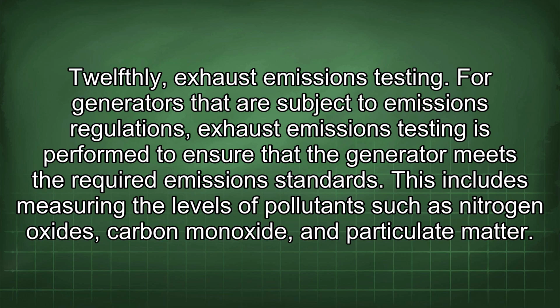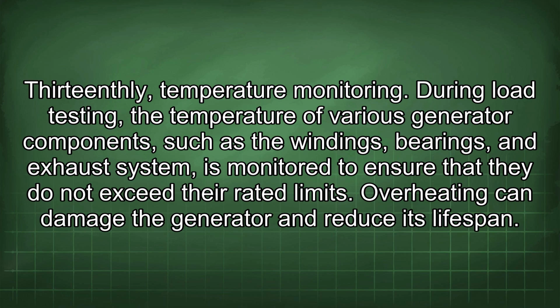For generators that are subject to emissions regulations, exhaust emissions testing is performed to ensure that the generator meets the required emissions standards. This includes measuring the levels of pollutants such as nitrogen oxides, carbon monoxide, and particulate matter. 13th, temperature monitoring. During load testing, the temperature of various generator components such as the windings, bearings, and exhaust system is monitored to ensure that they do not exceed the rated limit. Overheating can damage the generator and reduce its lifespan.